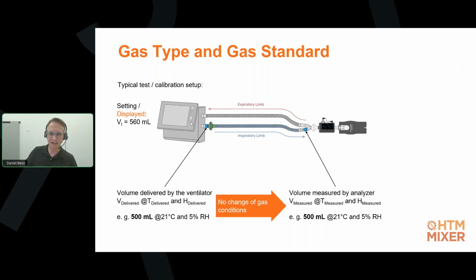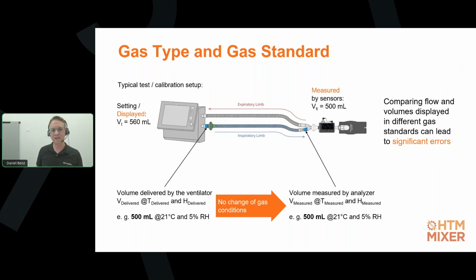And if that gas flow analyzer is then set to gas standard ATP, it's only going to measure 500 milliliters as a tidal volume. So what we do in this example is we compare different volumes in different gas standards, BTPS on the ventilator and ATP on our gas flow analyzer.